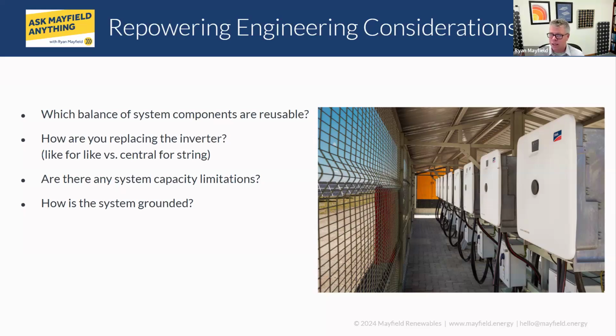The problem I see—and I'd open this up to you, Joe and Jose, if you have opinions—is that the 3741 listing is really attached to the racking system. If you're leaving the racking system in place and just replacing inverters, and trying to put the inverters up at the rooftop to meet 3741, you've kind of met it, but unless that racking system hasn't changed at all since installed and now carries a 3741 listing, you might have something there. But I still think the likelihood of that being the case is very, very low, and the way the system was installed probably wasn't to what the addendums require for those 3741 systems.